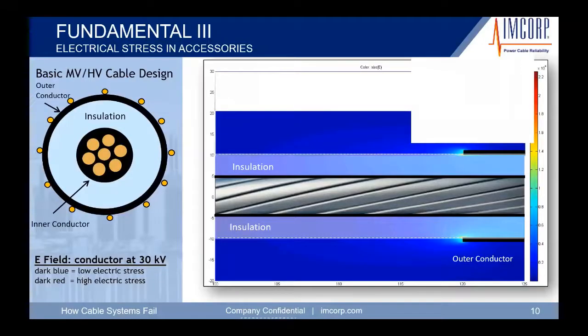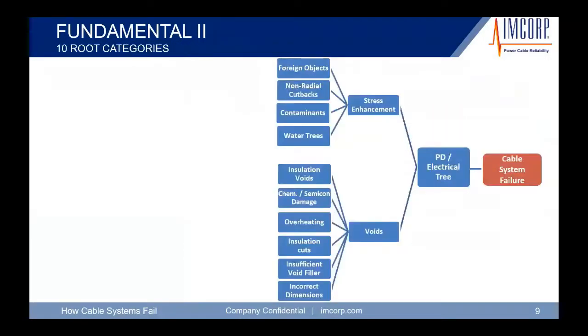So we talk about the different ways of stress enhancement and voids because these are all situations that can be avoidable. If the guys are properly trained in the field and they remove any foreign objects, the radial cutbacks are nice and smooth, there are no contaminants, the guys take a lot of careful steps to make sure that nothing is introduced. They clean the insulation properly, and they don't get the semicon on the insulation.